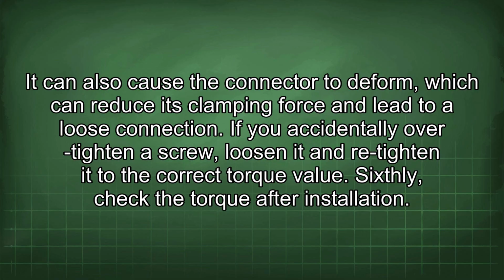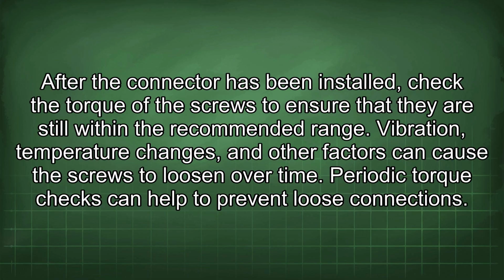Sixthly, check the torque after installation. After the connector has been installed, check the torque of the screws to ensure that they are still within the recommended range. Vibration, temperature changes, and other factors can cause the screws to loosen over time. Periodic torque checks can help to prevent loose connections.